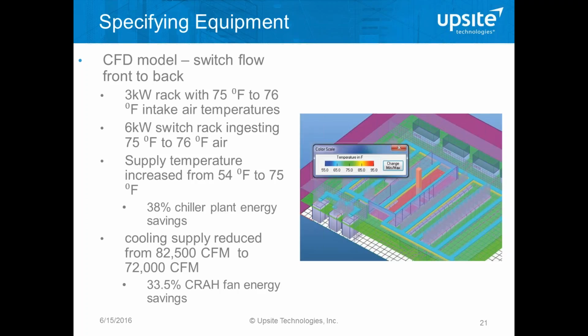So on the next slide, we can see the modifications that we made to the space by taking that cage with the open racks and changing the cage to a strictly vertical cage going to the ceiling, and taking out the open racks and replacing them with chimney cabinets, and then replacing the side breathing and top breathing storage and core switch cabinets in the middle of the data center with containment that made the data center view that equipment as if it were breathing front to rear. And these changes resulted in higher supply temperature but lower inlet temperatures, resulting in 38% chiller plant energy savings and a reduction in airflow to nearly 34% fan energy savings.